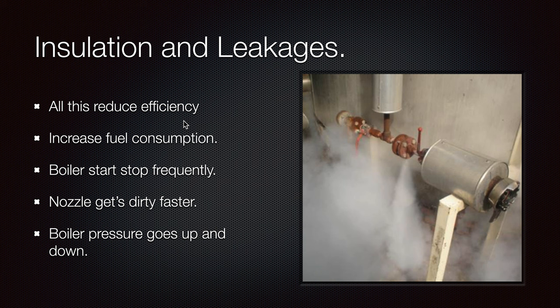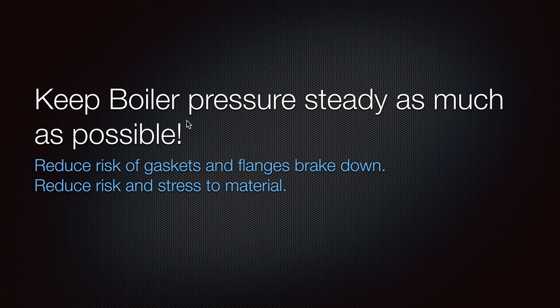From the perspective of thermal load — always reducing and increasing — the boiler is made to extend and shrink, which also reduces its life and operation. Keep boiler pressure as steady as possible. This will reduce the risk of gaskets and flanges breaking down, and reduce stress to the piping material and everything associated with that system.